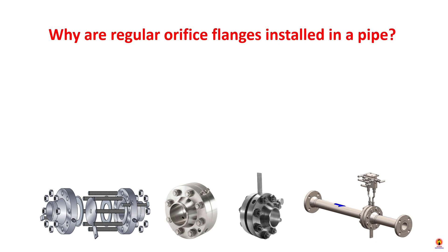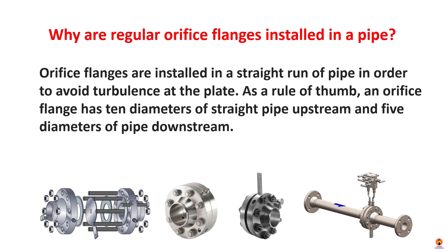Orifice flanges are installed in a straight line of pipe in order to avoid turbulence at the plate. As a rule of thumb, an orifice flange has 10 diameters of straight pipe upstream and 5 diameters of pipe downstream.